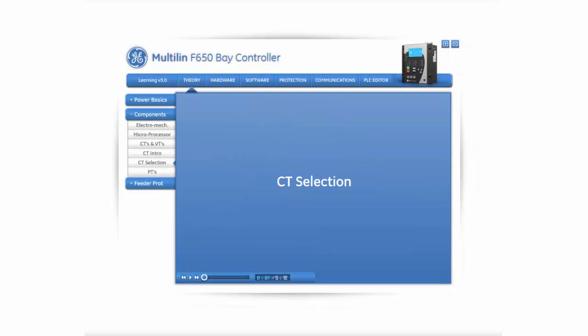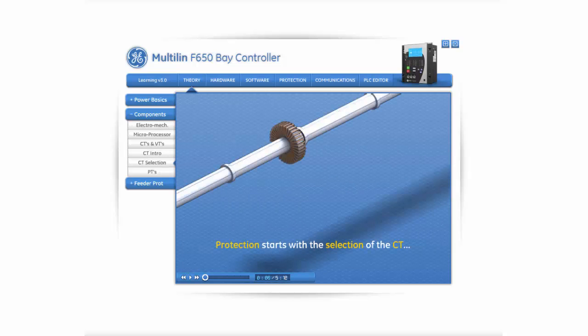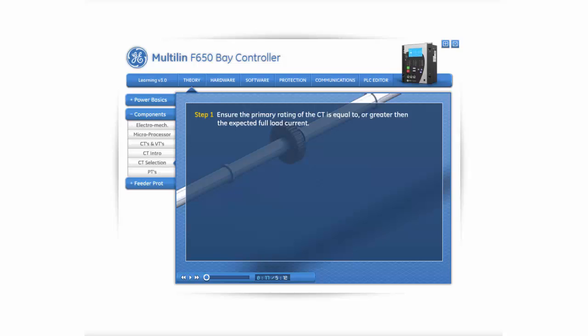CT selection. Proper protection starts with the selection of current transformers. The following is a simple procedure that can be used to check whether or not there is the possibility of CT saturation. The first step is to ensure that the primary rating of the current transformers is equal to or greater than the expected full load current. We can determine the primary rating of a CT by looking at its ratio. For a ratio of 100:5, a CT has a primary rating of 100, meaning that no more than 100 amps should be passed through the CT under normal operating conditions.